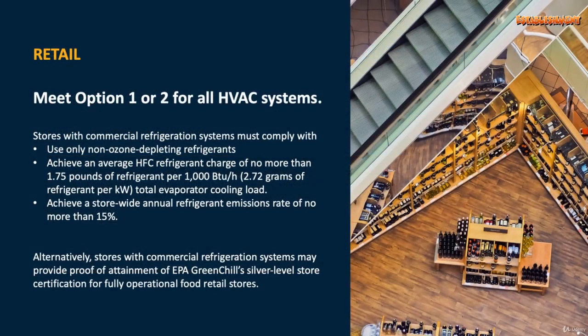Now for retail, meet option 1 or 2 for all HVAC systems. And stores with commercial refrigeration systems must comply with the following. Use only non-ozone-depleting refrigerants. Achieve an average HFC refrigerant charge of no more than 1.75 pounds of refrigerant per 1000 BTU per hour of total evaporator cooling load. And achieve a store-wide annual refrigerant emission rate of no more than 15%. Alternatively, stores with commercial refrigeration systems may provide proof of attainment of EPA GreenChill's silver level store certification for full operation of food retail stores. There are no performance period requirements.